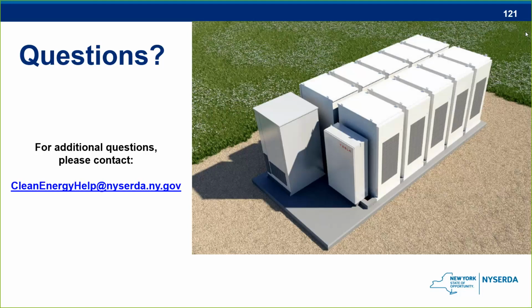Now this one, I answered it with the person who asked it, but I'll just reiterate for everyone else listening in. The question was, is 20 kilowatt hours the max for residential installations, even if it is a separated structure made specifically to house the system and at all proper distances? So for the residential installations, that 20 kilowatt hour threshold is going to be per unit, not aggregated. So for an accessory structure for a residential installation, the threshold aggregated is going to be 80 kilowatt hours. If you want to go larger than 80 kilowatt hours, it's going to then be subject to the fire code, not the residential code. Jen, I don't know if you or Paul have anything to add to that one, but I think that's pretty clear.